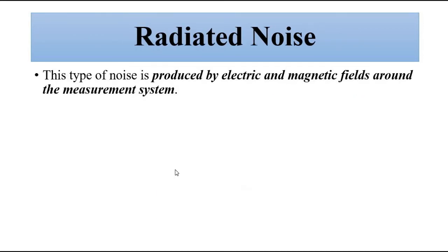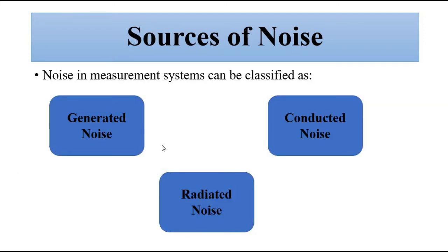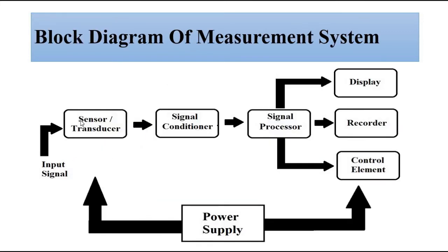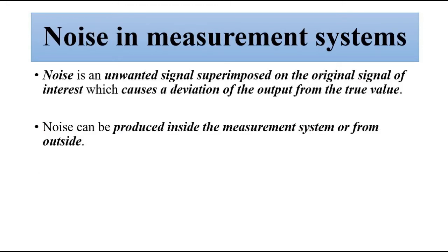Radiated noise is produced because of unwanted stray electromagnetic fields around the measurement system. In order to minimize the impact of these noise sources, various techniques are used: shielding, grounding, proper earthing, and proper encasing of the various subsystems — especially the sensors and transducers. Proper packaging, encapsulation, and encasing of components provides shielding from stray electromagnetic fields. Manufacturing techniques are also employed so that effects associated with the movement of atoms and electrons can be minimized.